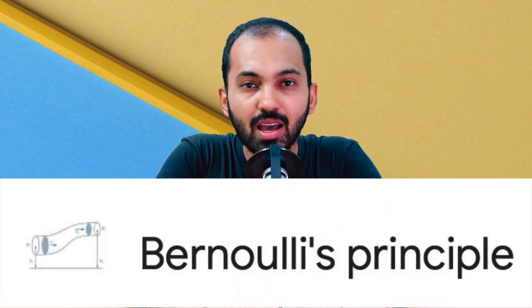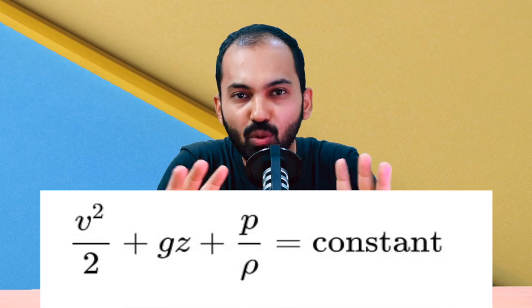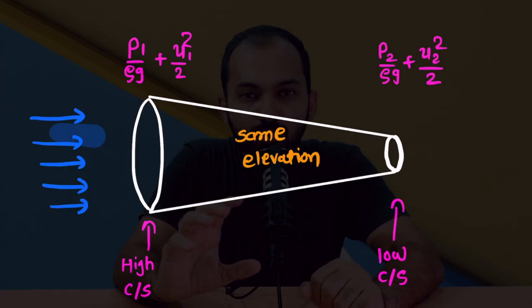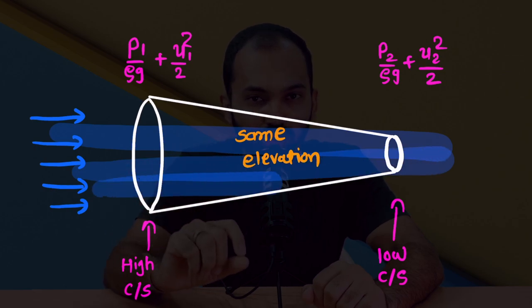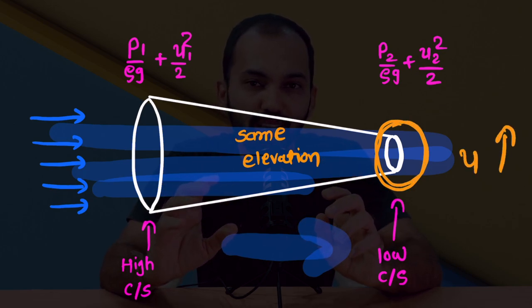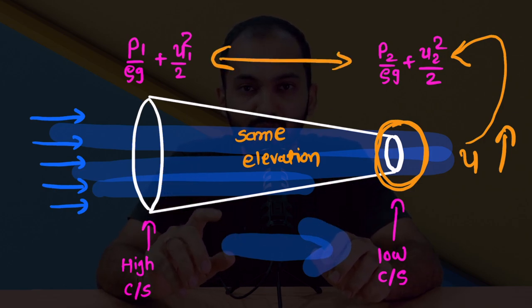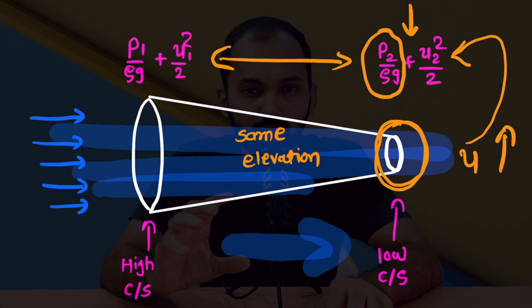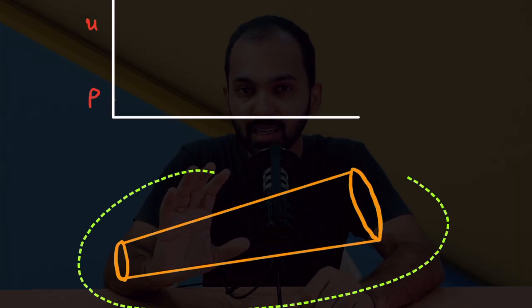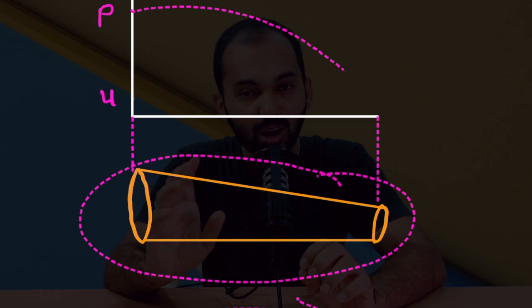The second concept is Bernoulli's Principle. As per the principle, the summation of mechanical energy is constant at any point in the pipe. If fluid flows from a higher cross-section area to a lower cross-section area, to balance the equation: as area increases, pressure increases and velocity reduces; as area decreases, pressure decreases and velocity increases. Both concepts are helpful to discuss NPSH available and cavitation.